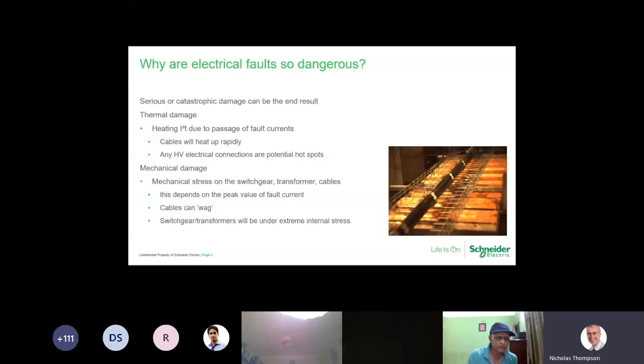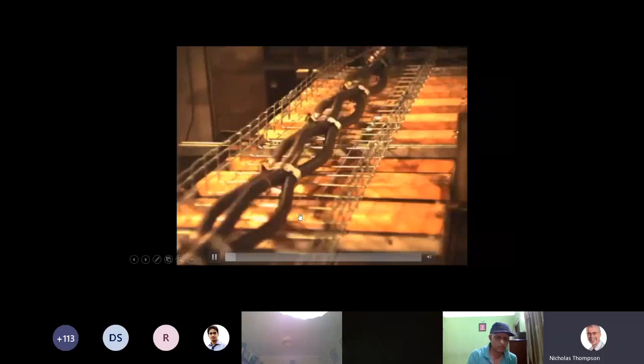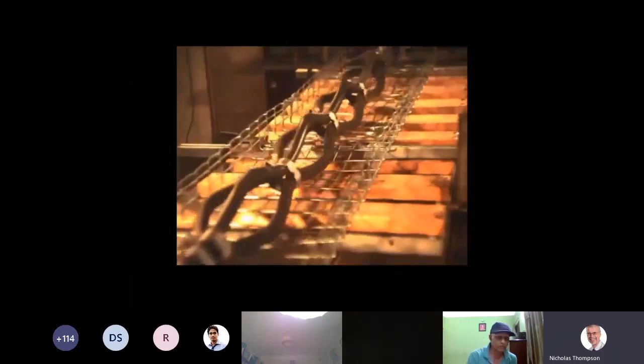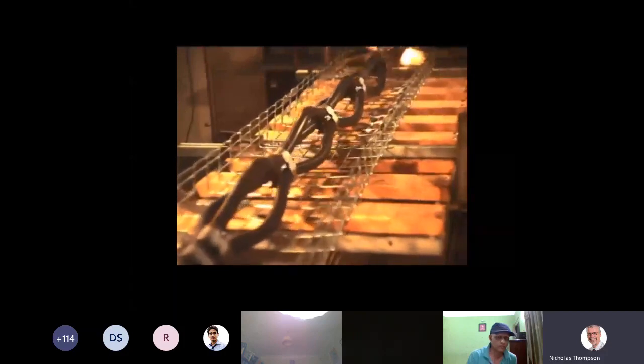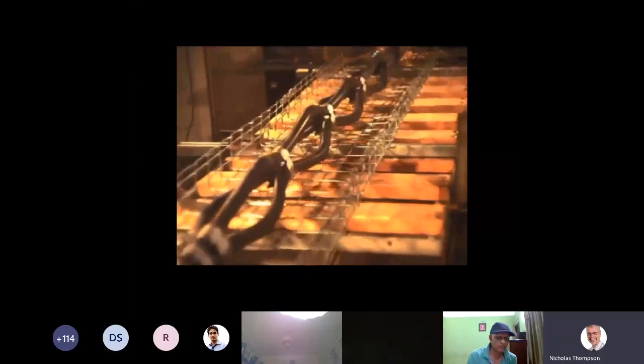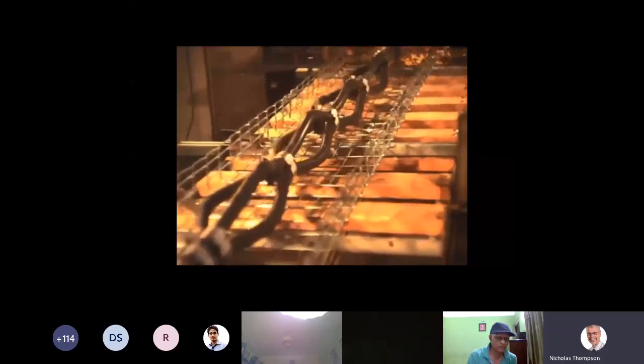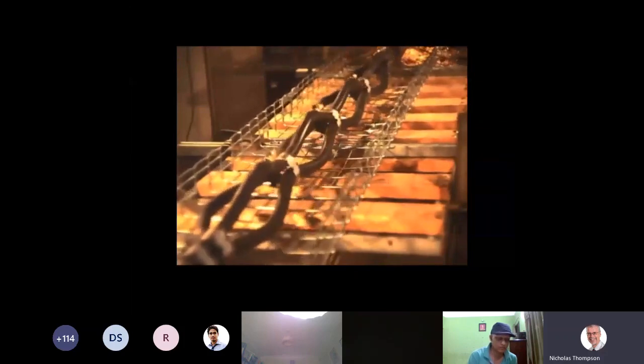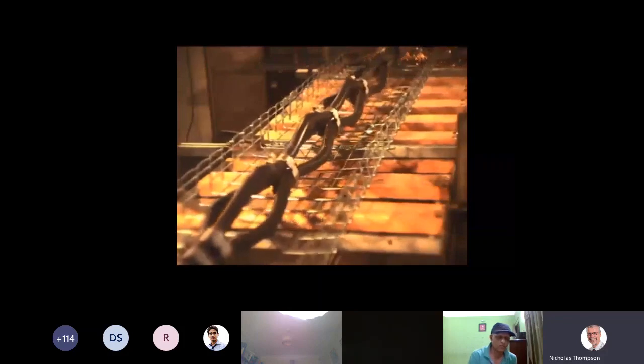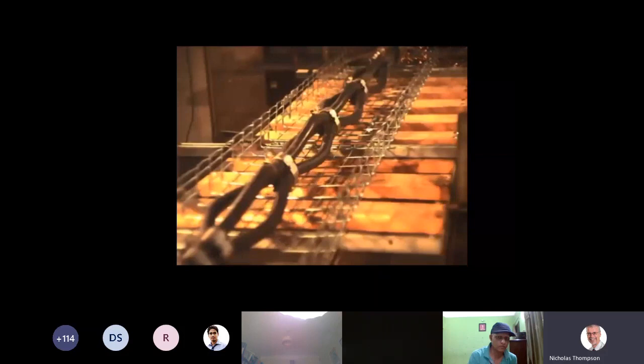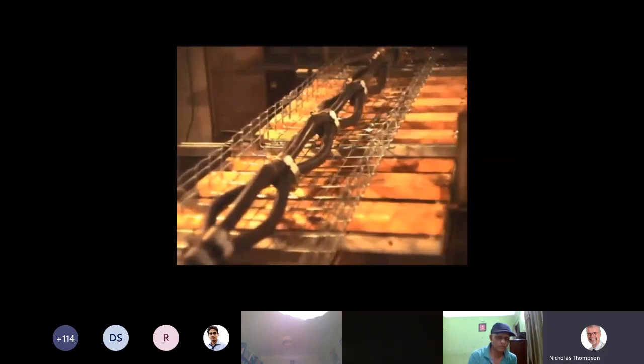Now, one thing that we don't associate electrical faults with is mechanical stresses. Switchgear literally may try and jump around given the electromechanical energy which is generated in there. And when I say cables can wag, this little video here is from a laboratory. I haven't said where it's come from. I've omitted that. It's from a YouTube video of cables under test in the lab using a very high voltage as fault level passing through it. So you can see how they are literally jumping around, causing the cable tray to twist and bounce around, when in real life that cable tray may seem fairly rigid. That's no different to switchgear or transformers.